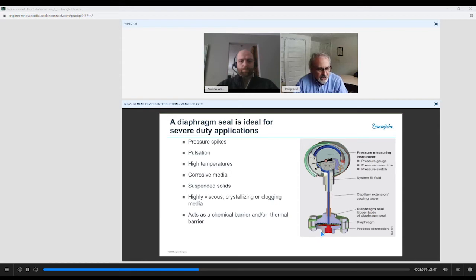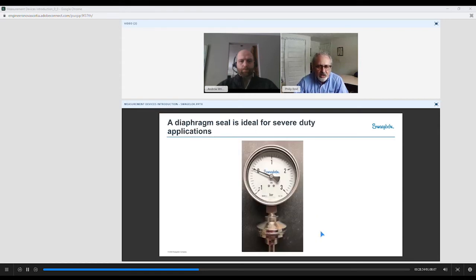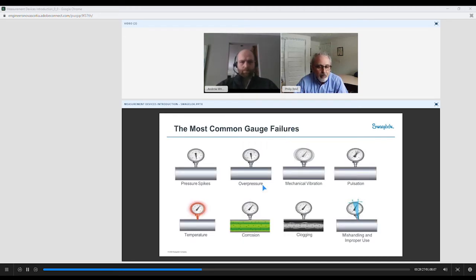So lots of applications, and we'll just have a closer look here at an actual one. We had this picture up a little bit earlier, but this is what the seal would look like. This is a very short capillary. This could be lengthened out. Just back to this gauge for a minute. This happens to be a compound gauge, single scale, reading in bar only, and all the internals of this gauge are 316L for this application. So this is a positive pressure, negative pressure gauge, and that would be a compound gauge, but not dual scale.